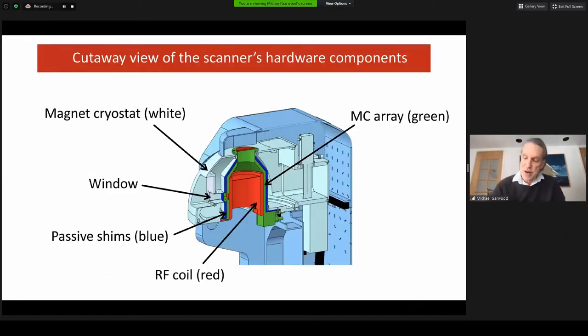In this cutaway view of the scanner, I'd like to draw your attention to another innovative hardware component indicated in green which is a multi-coil or MC array used both for improving field uniformity and for spatial encoding the MRI signals. The MC array serves the role of both shim coils and gradient coils that exist in standard MRI scanners, but the MC array provides greater flexibility for dynamically shaping the magnetic field.